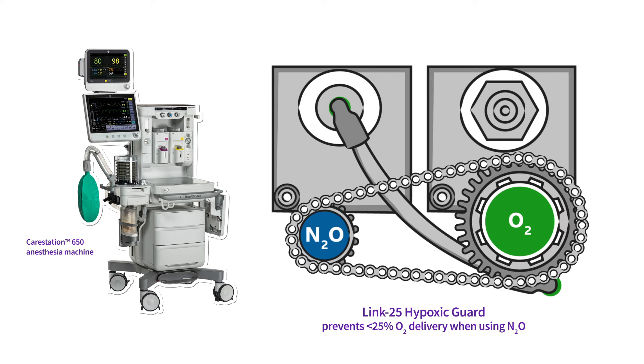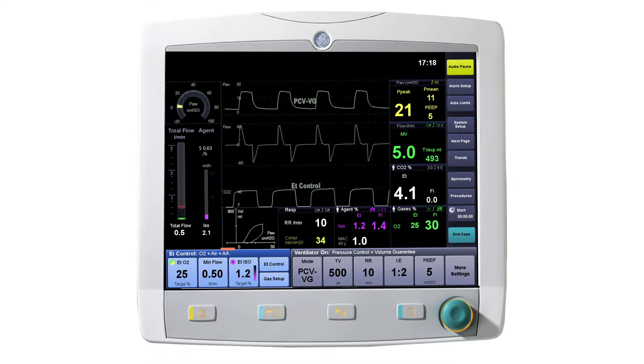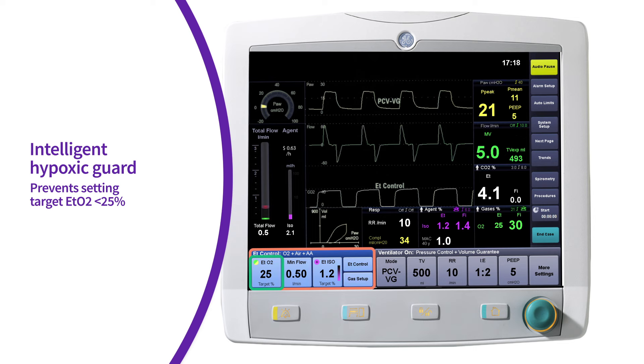With manually controlled circle anesthesia systems, there are conventional hypoxic guards that control the oxygen percentage in the fresh gas flow and not the circuit FiO2, which could result in hypoxic levels of inspired oxygen. GE Healthcare's Aisys CS2 end-tidal control contains an intelligent hypoxic guard, since the oxygen percentage is controlled at the patient level by automatically compensating for metabolic rate changes, ensuring targeted end-tidal values.